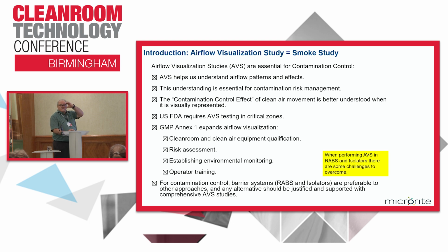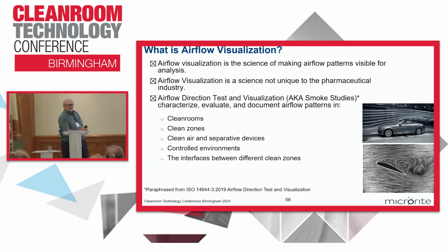And interesting things to consider when we talk about doing airflow visualization in both RABS and isolators: they have some challenges that we have to overcome. But what is airflow visualization? It's a science of making airflow patterns visible for analysis. It's a science that's actually not unique to clean rooms or to pharmaceutical manufacturing. Airflow direction test and visualization, aka smoke studies, and I paraphrase this from ISO 14644 Part 3, is useful to document, evaluate, and characterize airflow patterns in clean rooms, clean zones, clean air and separated devices, controlled environments, and the interfaces between zones.